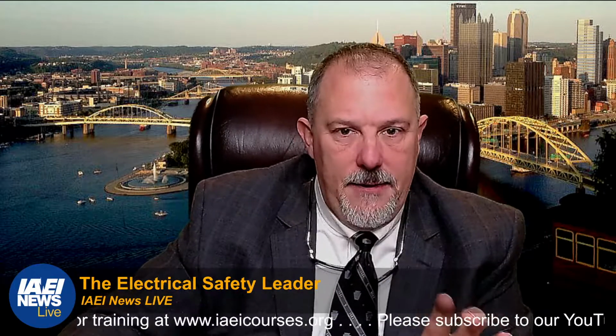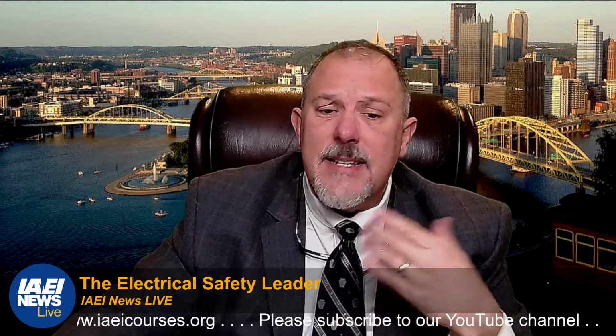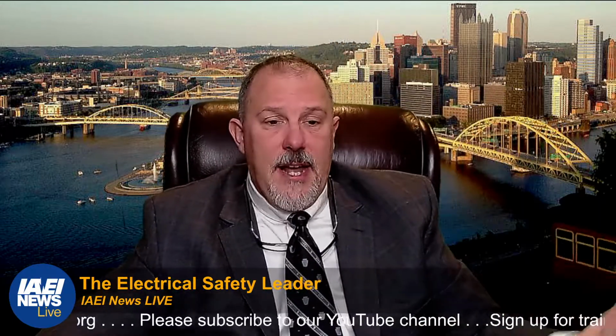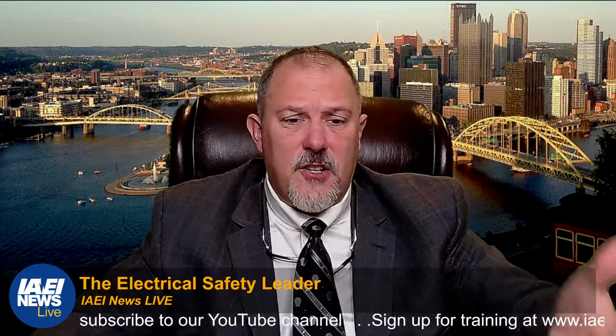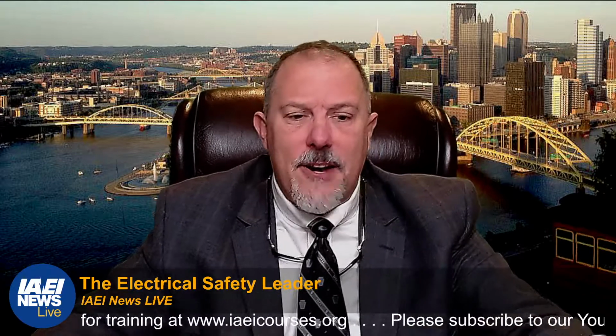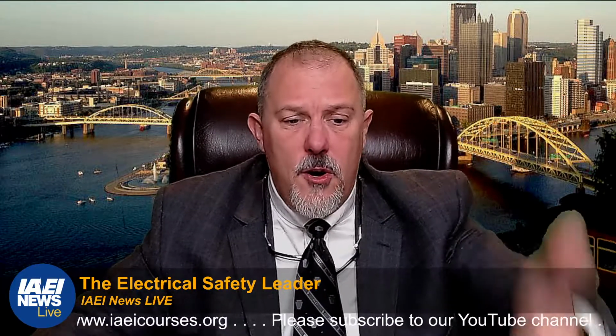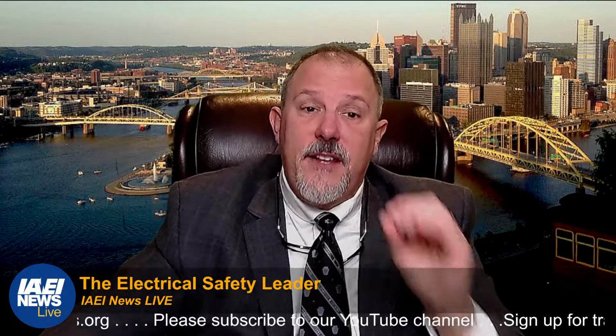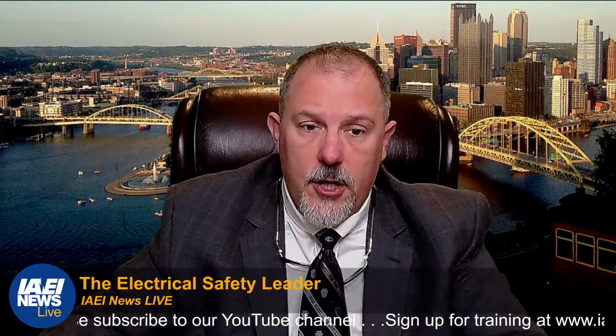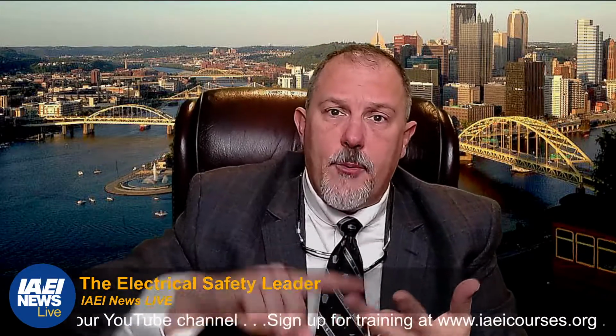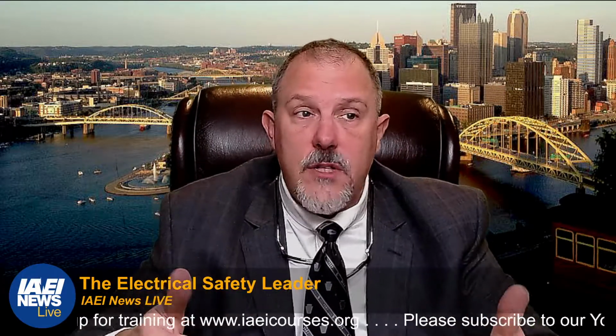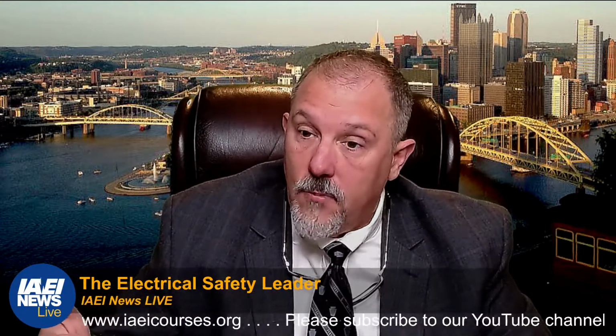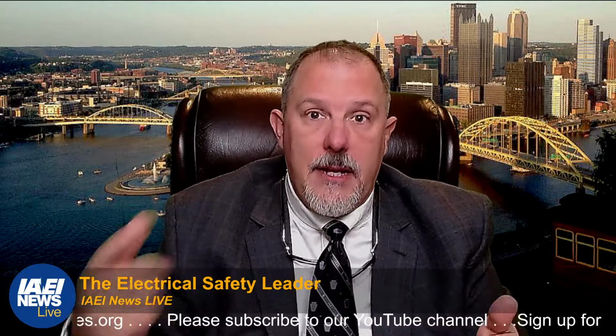So Chapter 10 tells us, for the product that you're looking at, panel boards, switchboards, power breakers, insulated case circuit breakers, fuses, high voltage substation insulators, switchgear assemblies, surge arresters, capacitors, batteries and chargers, protective relays. We can go on and on, all the different products. They tell you the different types of test, the scope of your work, whether you are doing thermography or mechanical operation, a visual inspection, or maintaining and testing it. And a test could be a physical test, it could be an electrical test, right? For a breaker, you might say, hey, you need to make sure that it opens on an overcurrent.